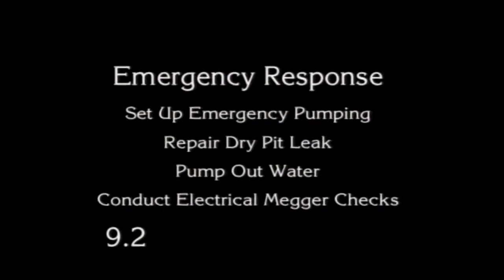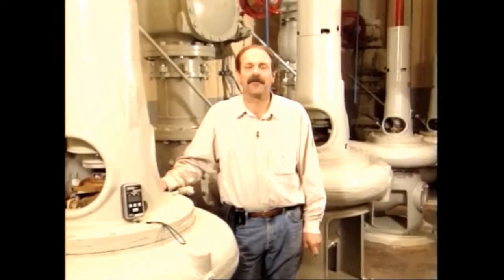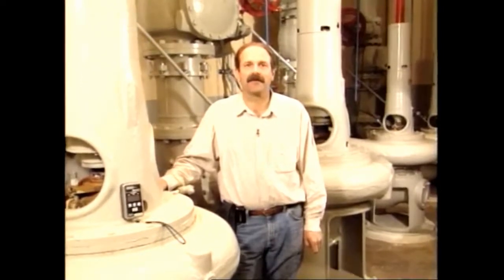Conduct electrical megger checks on electrical circuits and motors. A megger check will help you determine whether electrical circuits or motors can be operated or need to be repaired. A megger is an instrument used to check electrical resistance on motors, feeders, bus bar systems, branch feeder wiring, and grounds.